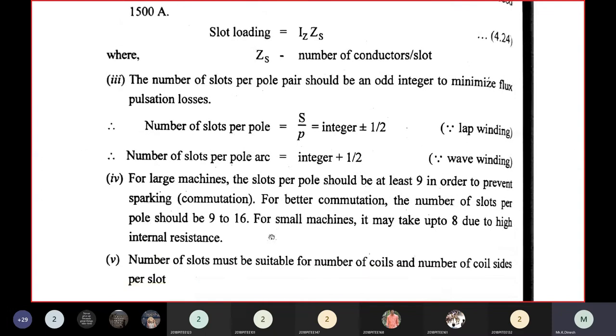In large machines, slots per pole should be at least 9 to prevent commutation problems. Generally, for better commutation, the number of slots per pole should be 9 to 16. For smaller machines, we may take 8.